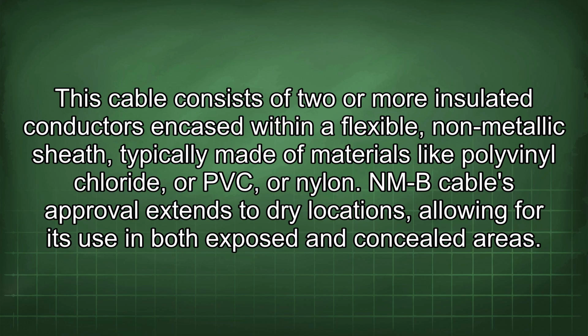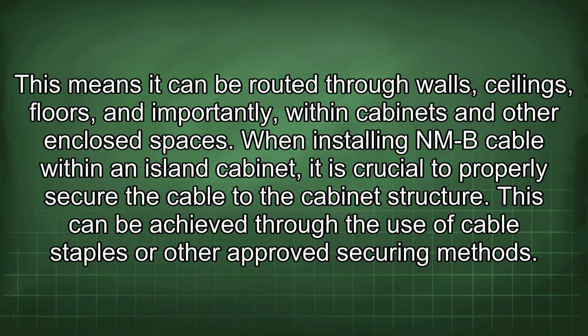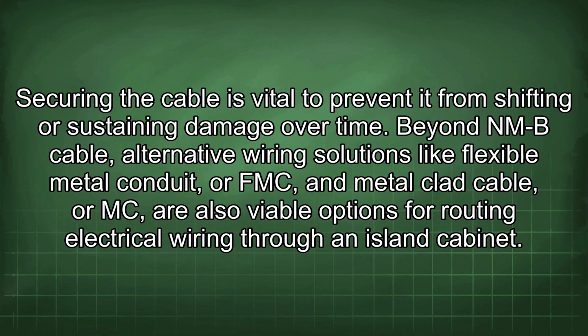NMB cable's approval extends to dry locations, allowing for its use in both exposed and concealed areas. This means it can be routed through walls, ceilings, floors, and importantly, within cabinets and other enclosed spaces. When installing NMB cable within an island cabinet, it is crucial to properly secure the cable to the cabinet structure. This can be achieved through the use of cable staples or other approved securing methods. Securing the cable is vital to prevent it from shifting or sustaining damage over time.